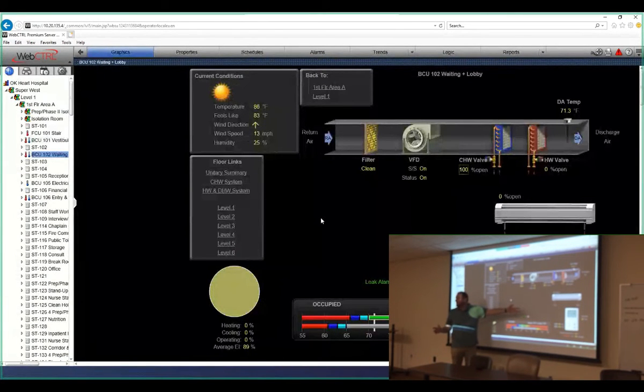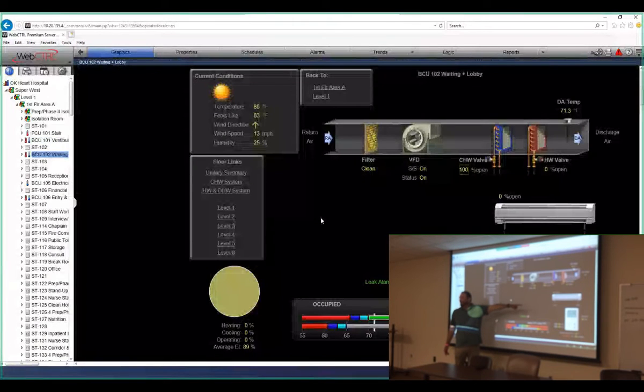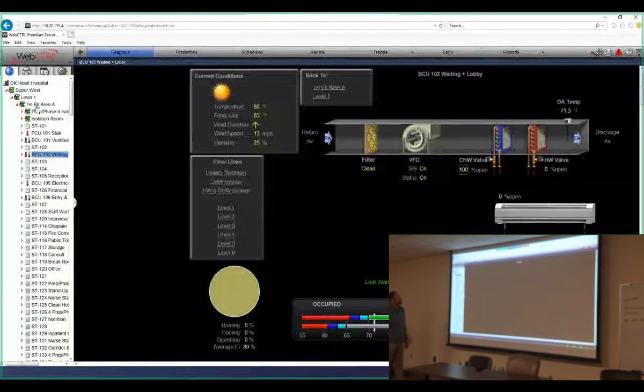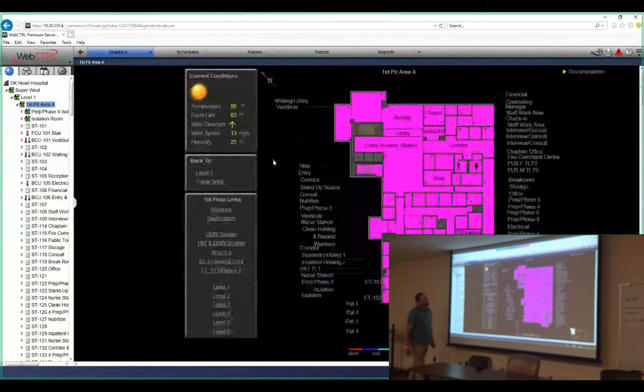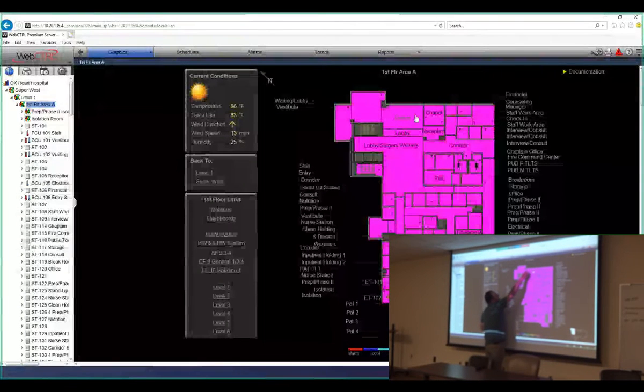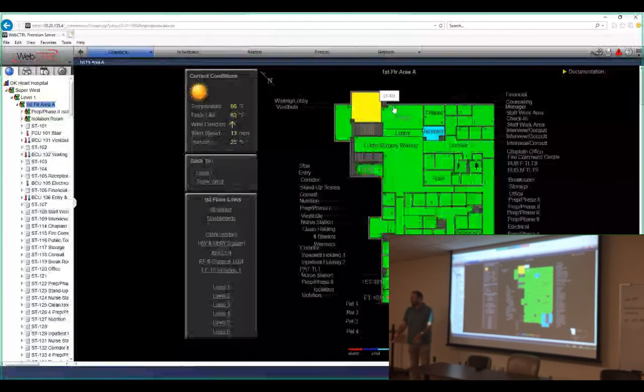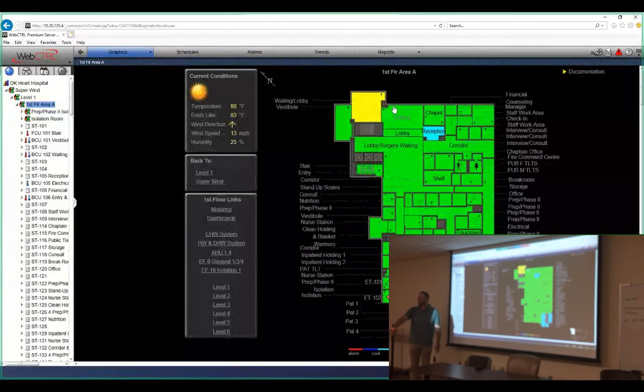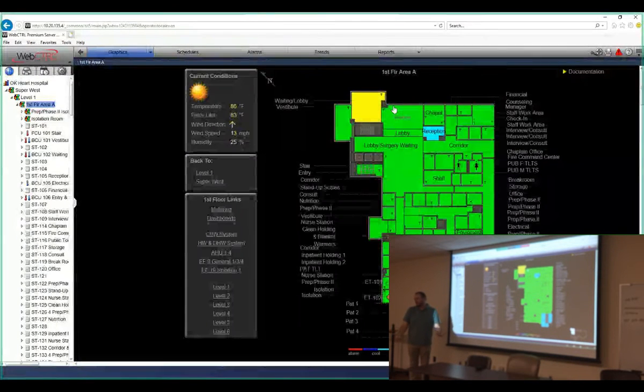And so in like that vestibule, the waiting area, those units are typical, and this is a waiting area, so we can actually kill two birds with one stone here. This is the radiant heat that's on the blower coil unit. We go back to that first floor area A graphic. It's kind of hard to see, but out here along this wall there's radiant heat right down on the floor. It's just a fin tube radiant heater, and that's along the glass, and it's going to help heat that glass in the wintertime. The blower coil unit's going to take care of it, but once we drop below that set point, we're going to start opening that radiant heat also.